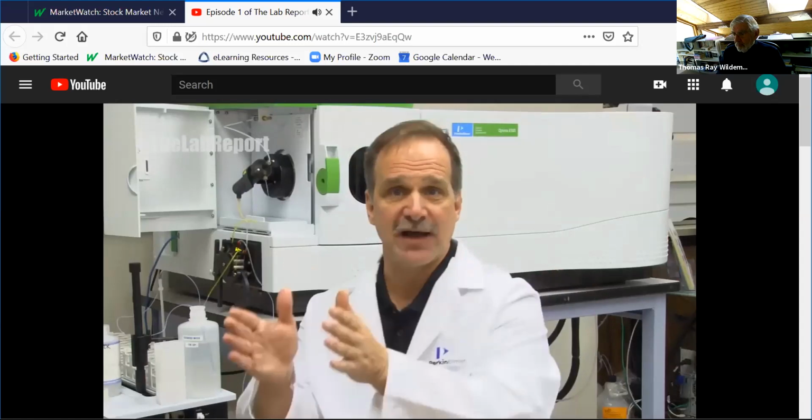Instead of about 90 seconds to rinse all the tubing out, this system only needs about 7 to 10 seconds to rinse out that loop. Now, we used an ESI fast system in this application note that basically reduces your sample to sample time by half. Now, for environmental laboratories, that's a huge productivity gain because you get paid per sample, right?